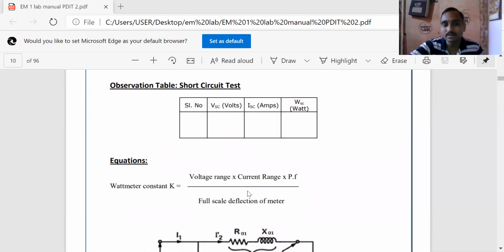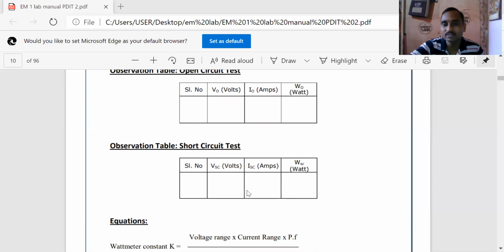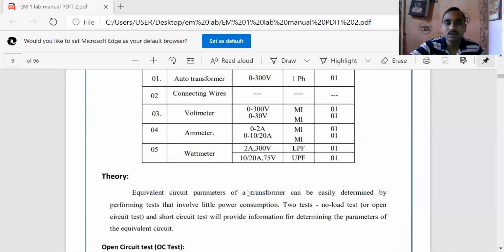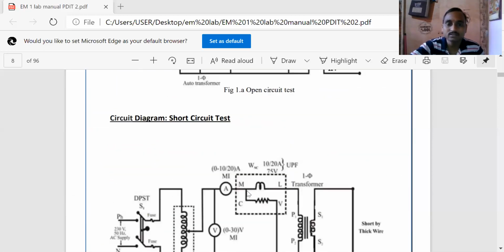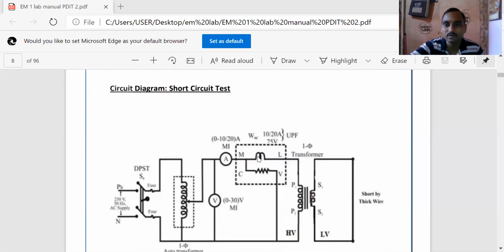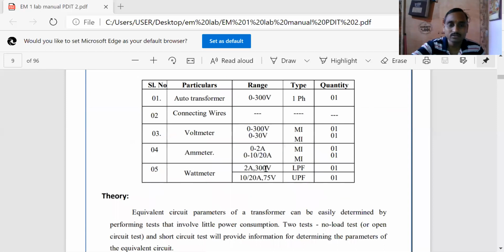Suppose you use the wattmeter individually. A multifunction meter means it consists of all the meters: voltmeter, ammeter, wattmeter, power factor meter, frequency meter, everything. Every meter is a digital meter. So no need to find out the wattmeter constant if you connect through the multifunction meter, or you can do the connection individually through a separate voltmeter, separate ammeter, separate wattmeter. So you need to find out the wattmeter constant. How to find out the wattmeter constant?